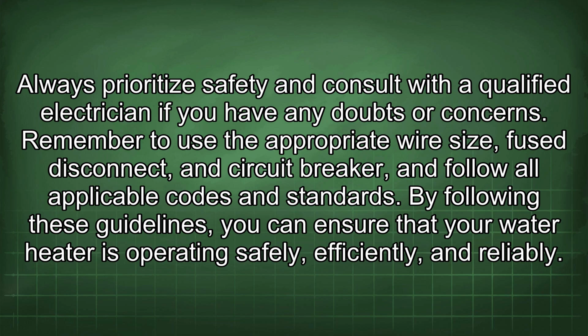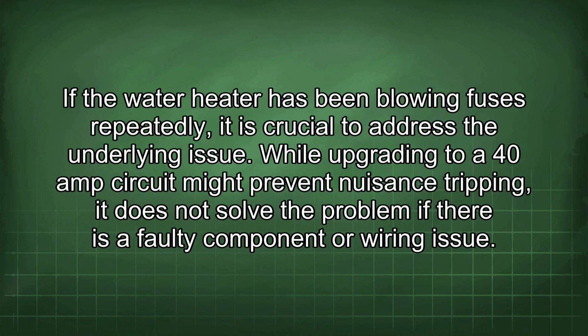Remember to use the appropriate wire size, fused disconnect, and circuit breaker, and follow all applicable codes and standards. By following these guidelines, you can ensure that your water heater is operating safely, efficiently, and reliably. If the water heater has been blowing fuses repeatedly, it is crucial to address the underlying issue. While upgrading to a 40-amp circuit might prevent nuisance tripping, it does not solve the problem if there is a faulty component or wiring issue.